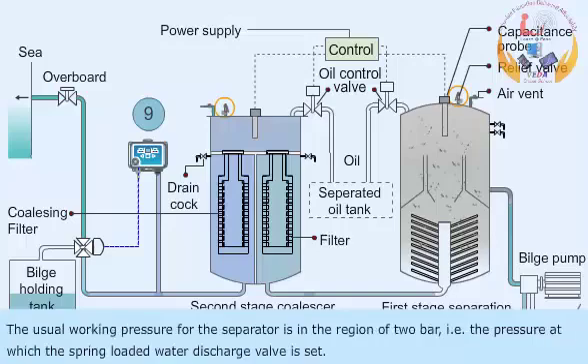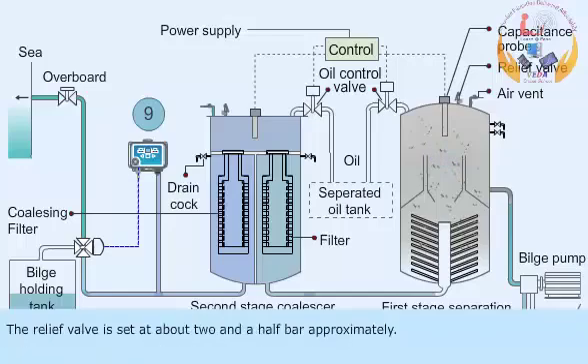The usual working pressure for the separator is in the region of 2 bar, which is the pressure at which the spring-loaded water discharge valve is set. The relief valve is set at approximately 2.5 bar.